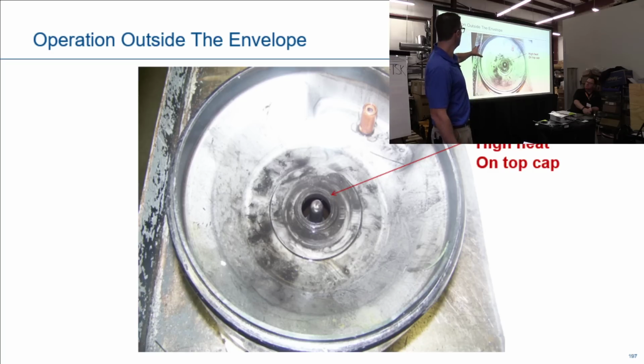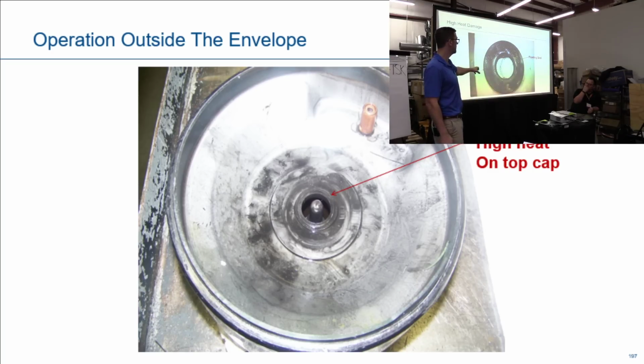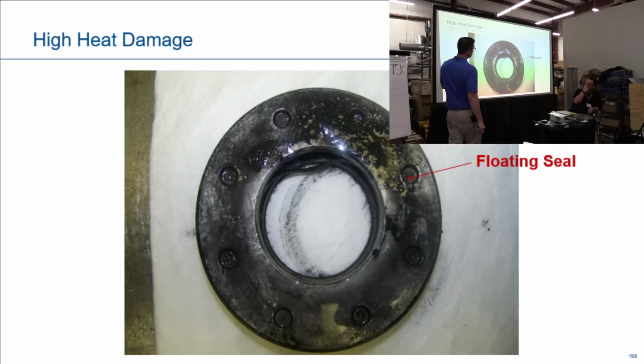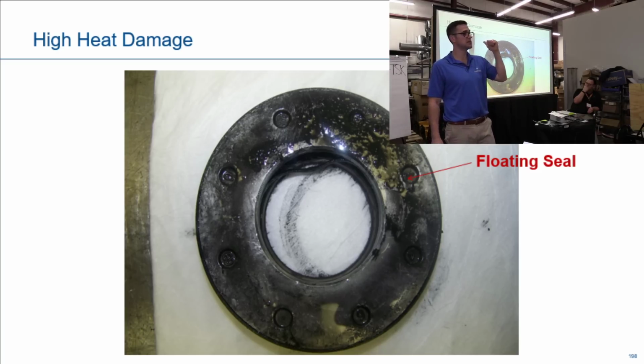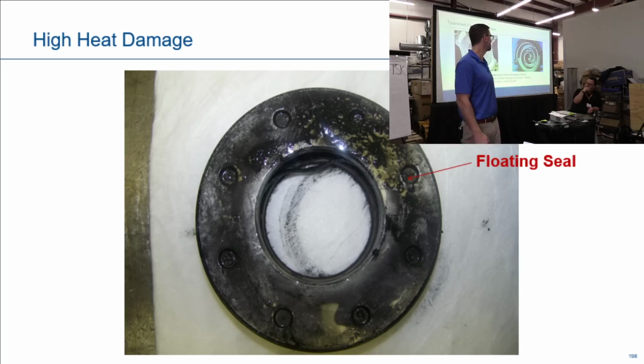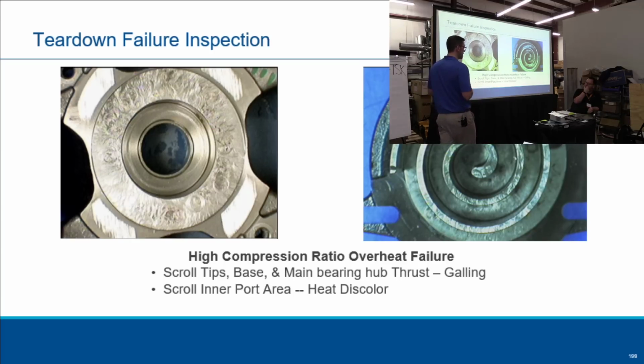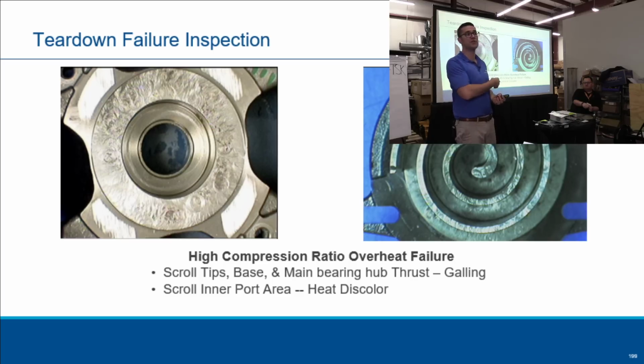Okay, inside of a scroll, you get a lot of heat up in there, heat to the top cap. This is the floating seal. This is actually the seal ripped because of the heat. It's a damaged seal. So is that compressor ever going to pump this scroll? That's not going to pump. Okay, then you look inside. If you cut open a scroll and it looks super dry, that refrigerant through your system should always be carrying oil. Oil is always moving through the system with your refrigerant. You look inside the scroll set and it looks like this and it's super dry. Was there any oil in there?